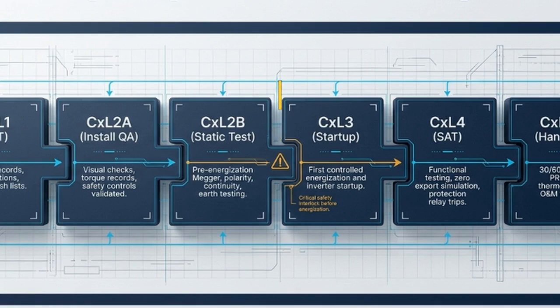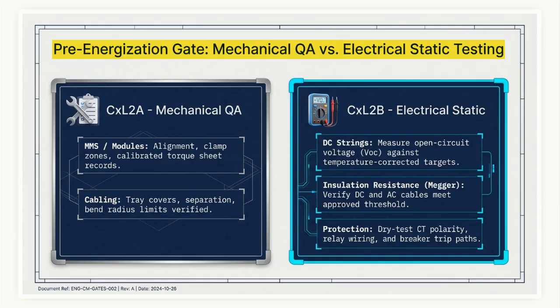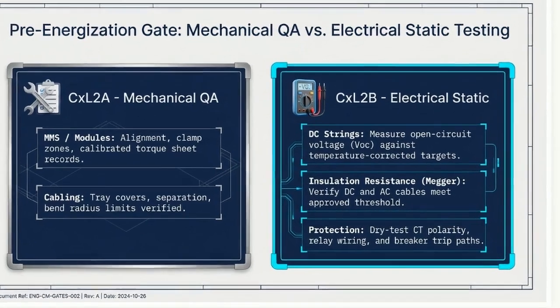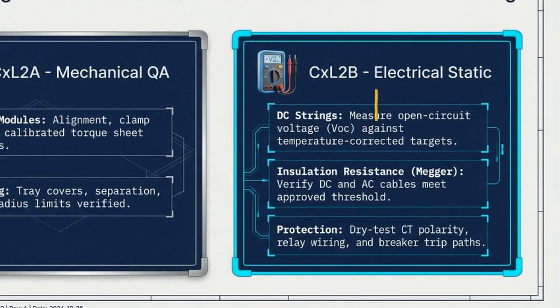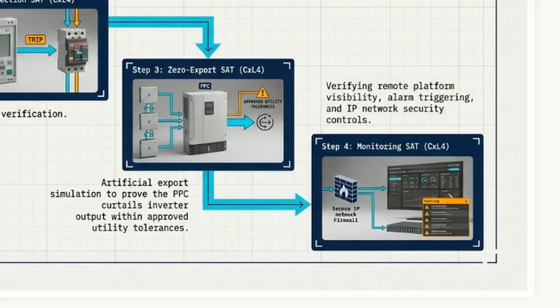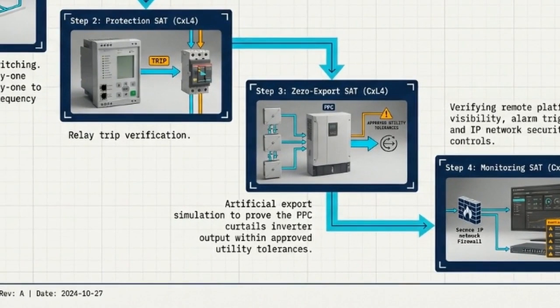This chart contrasts the mechanical checks of Stage 2A with the static electrical proofs of Stage 2B. Before any power is authorized, technicians use high-voltage Megger testing to detect macroscopic hidden ground faults while the system is still dead. The climax of dynamic validation occurs in stages 3 and 4. We execute a sequential one-by-one inverter startup, followed by an artificial export simulation. This proves the power plant controller's zero export system successfully throttles output under live load.